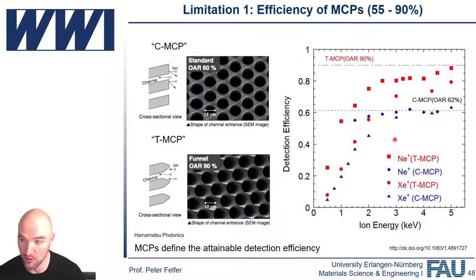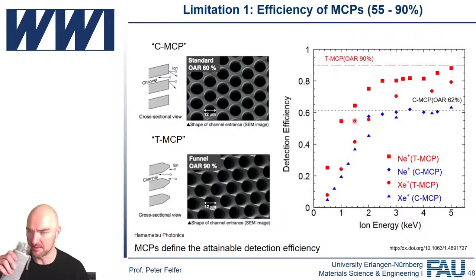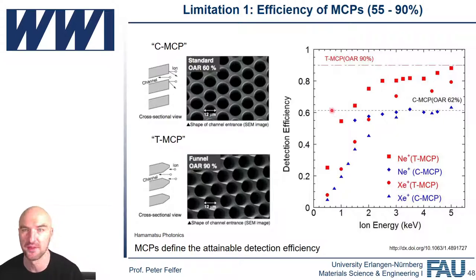materials with very low evaporation field, maybe some nanowires or something like that, that if you have the funnel MCPs, you know that the saturation at those low voltages might not be full. I mean, below 2 kV, this also starts applying to regular MCPs. Yeah, so if you've got extremely sharp samples, nanowires, something like that, this can be an issue.